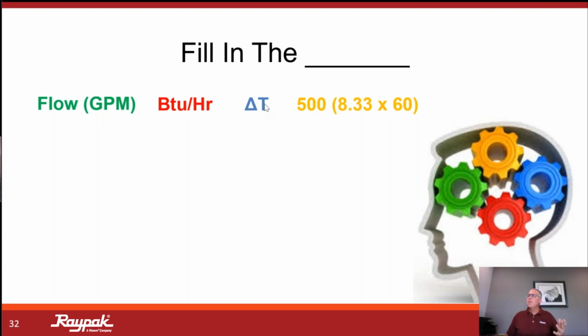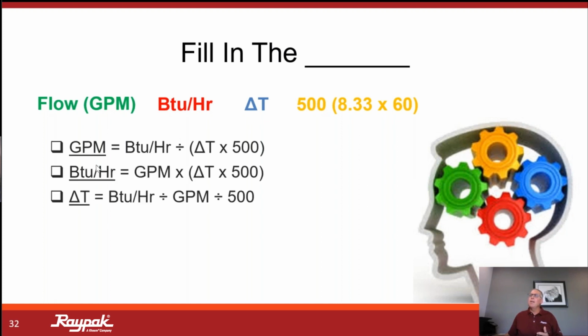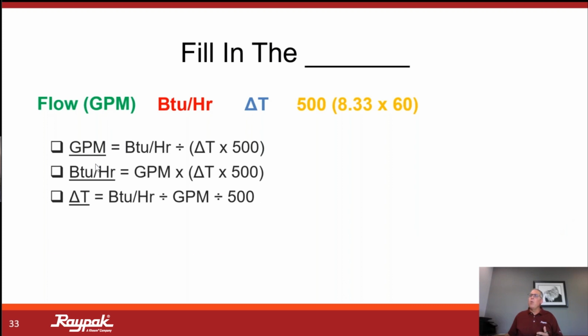So here's where it becomes important. Again, don't get hung up on this verbiage of a constant. This is just a known value of the weight of a gallon of water times 60 minutes. It's very well known in our industry. For you math majors out there, this actually equals 499.8, but for simple math and for practical terms, we use 500 as a constant. Well, the value proposition is if we know 2 of these values plus the constant, we'll populate that 4th value, right?